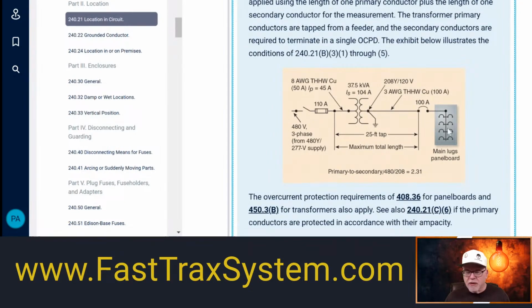But here it's all broken out, so it's easy for you to see, instead of putting this breaker here in this panel, because you could have a separate application where you hit a breaker in a separate individual enclosure, and then you hit a panelboard that's in an enclosure, or they could all be incorporated in one. It's up to your design professional. But this just shows you an example here, so let's do theirs real quick. So here is their total 25 feet. So it's not more than 25 feet, okay? And that's the total maximum length.